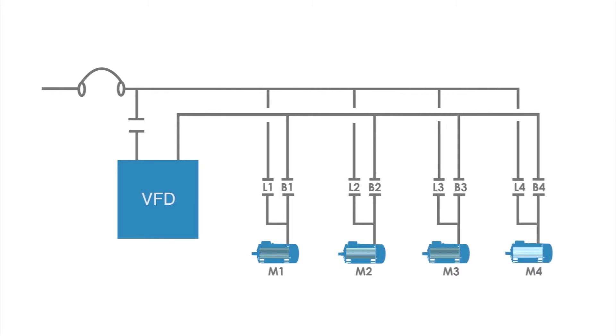Generally, the application requires the use of a VFD to start the motor. Once the motor is at full speed, the VFD will synchronize the motor voltage to the incoming line voltage by matching the frequency of the motor to the incoming line. By adjusting the speed of the motor, the waveforms are synchronized.